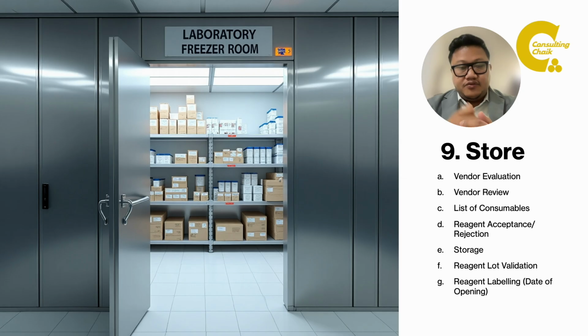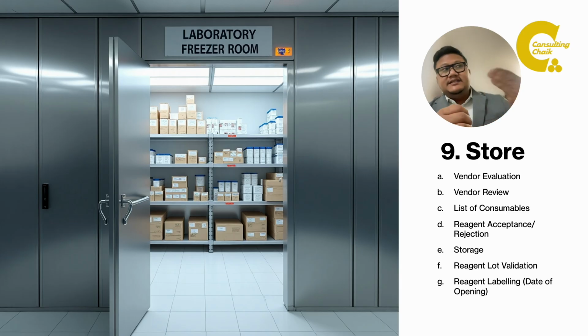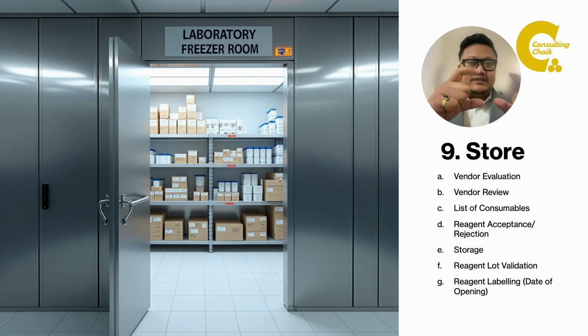Then before using the reagents in the equipment, you need to do a reagent lot validation. A reagent lot validation is a process where you compare the last accepted reagent with the new accepted reagent. There you compare two things. One is the control. So in the last reagent, what the control result was. For that, you just need to refer to the range given by the controls, whether the result is coming in the acceptable range or not when you use the new reagent.